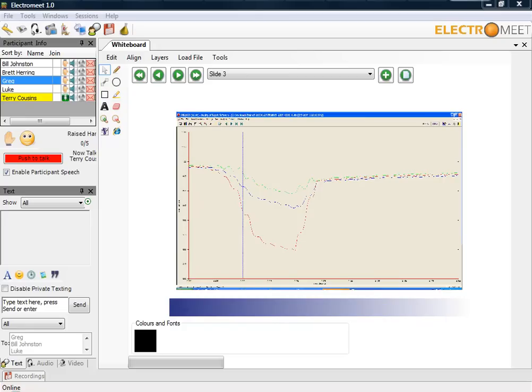If we look at an actual recording from a system, we will see that there we have the reduction. You can see quite a substantial reduction in voltage on the three-phase graph on the red phase.